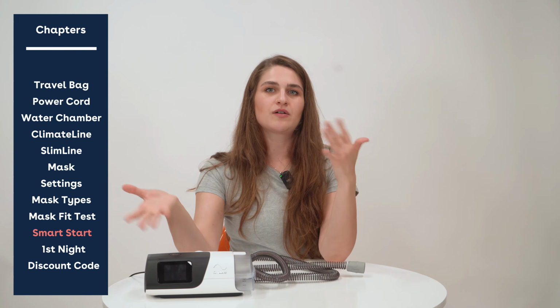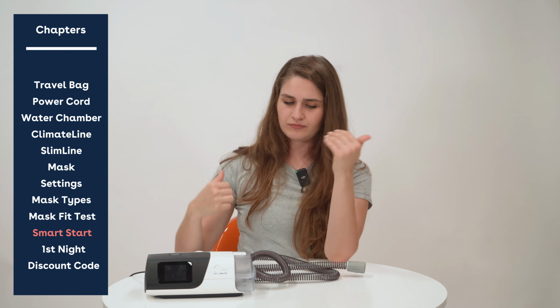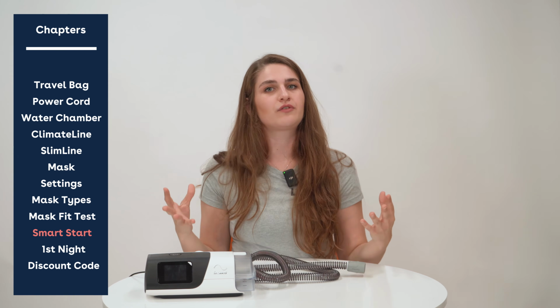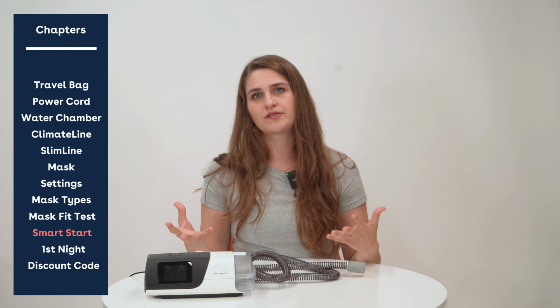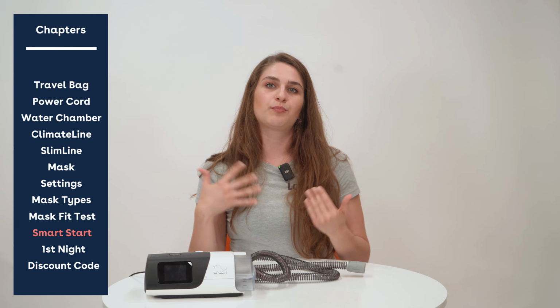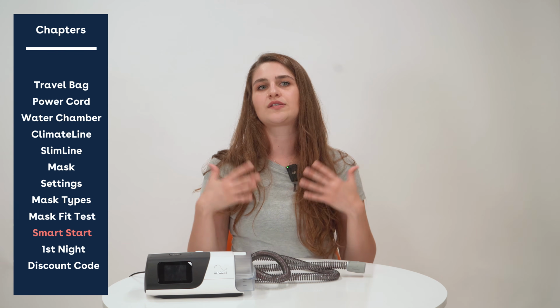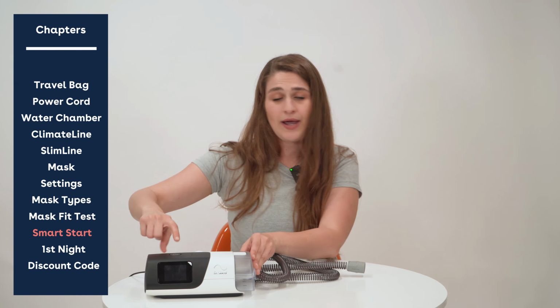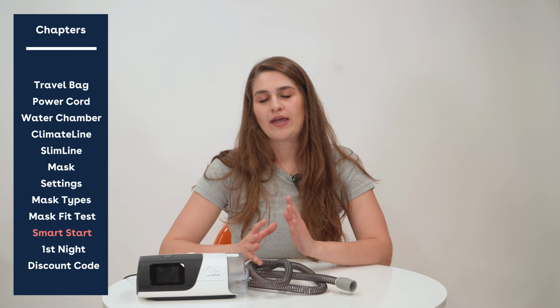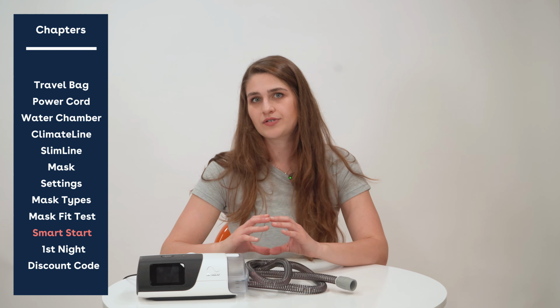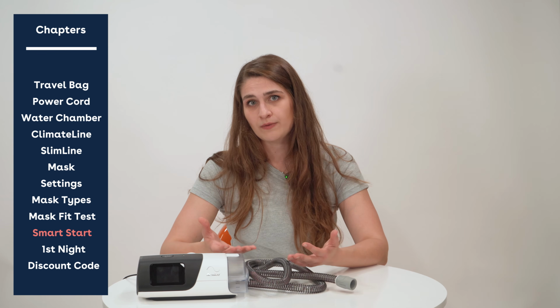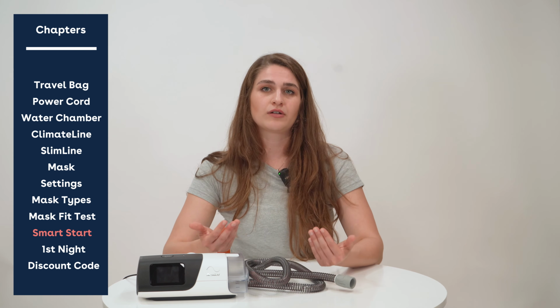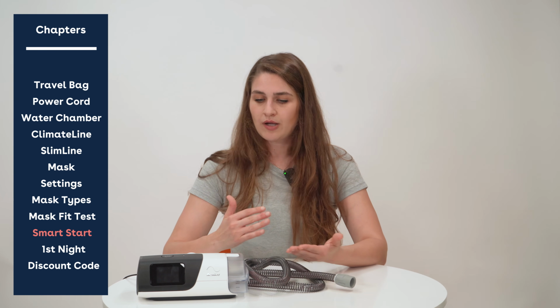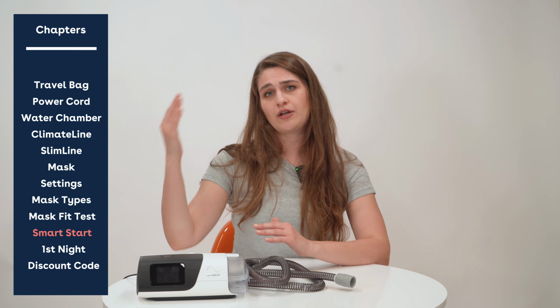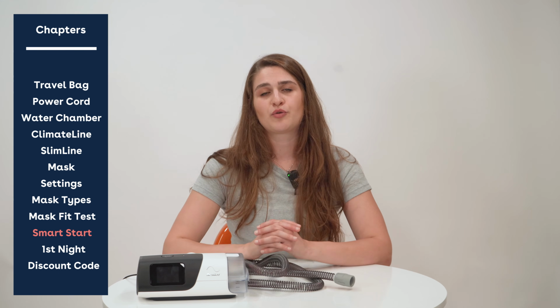And now that you're all set, let's go ahead and get you started on therapy for bedtime tonight. So when you are using your mask, there is a preloaded feature called Smart Start and Smart Stop on the device. That means when you put the mask on and take a few deep breaths, the device will automatically turn on because it's sensing your effort to breathe. So there is a power button at the top of the device, but you actually don't need to press it at all. There is a feature called ramp on your device. And so you might notice that when your machine starts out, it starts at the lowest pressure possible, which is a pressure of 4. And it'll typically stay there until you've actually fallen asleep and have a breathing episode. So when it comes to ramp, your pressures stay low and they will gradually increase throughout the night and auto adjust based on your prescribed settings.